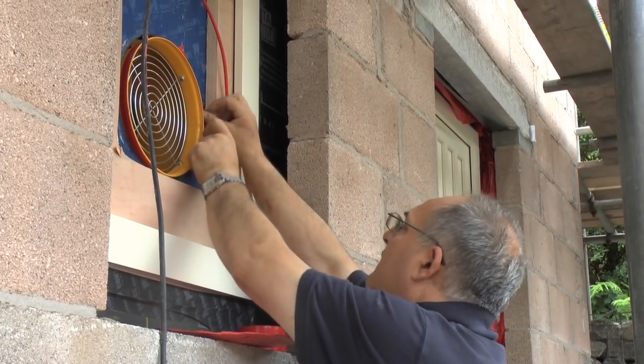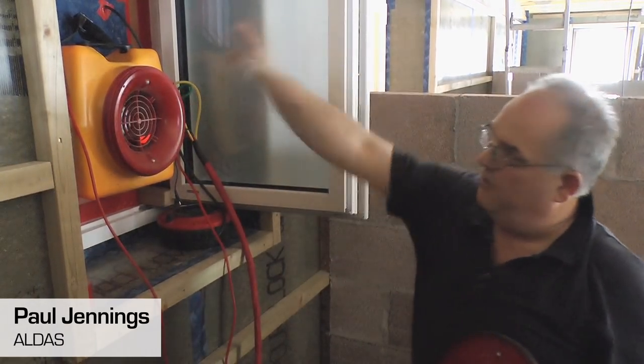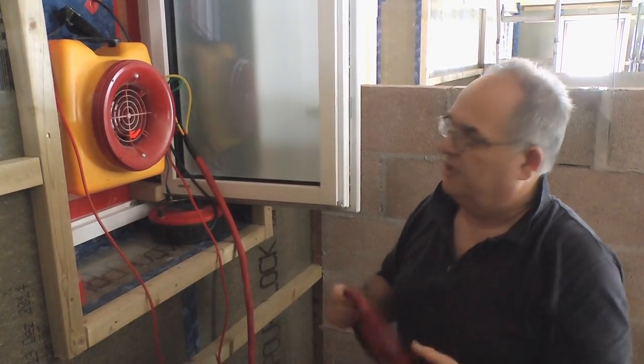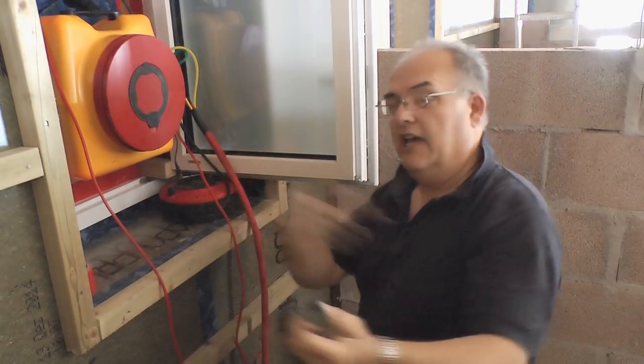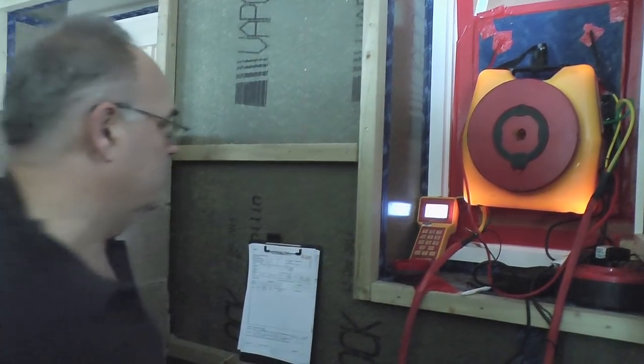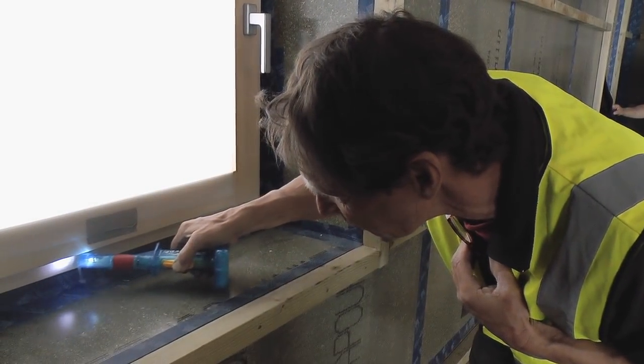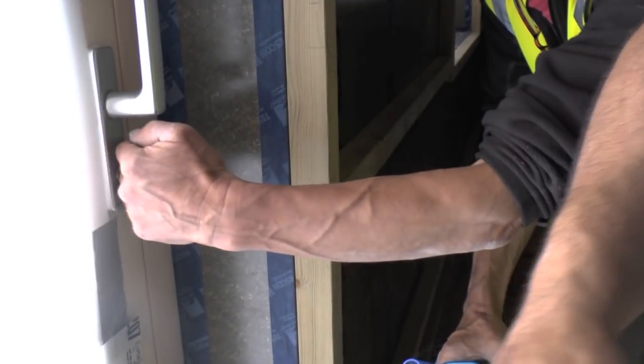We're here to do the preliminary test on this new build Passive House. There's a little fan in there that takes air out of the building. We start off by depressurising, so the building pressure goes lower. At which point if there's a leak, air comes back in through the gaps. The top reading is the difference between inside and outside. Now we're up to 50 pascals. It's a smoke gun — you can detect air leakage if the smoke deflects. I can't even feel it without the gun. I don't think you're going to have any danger of failing here.